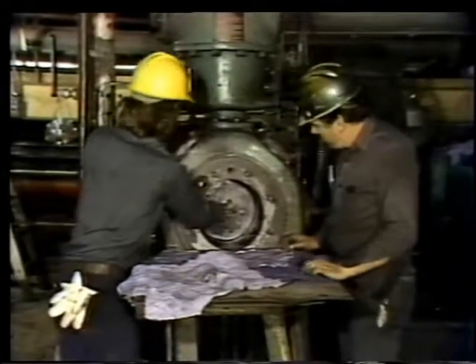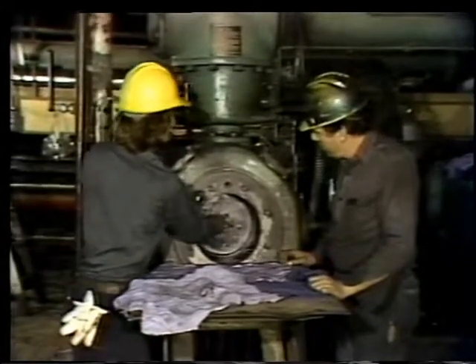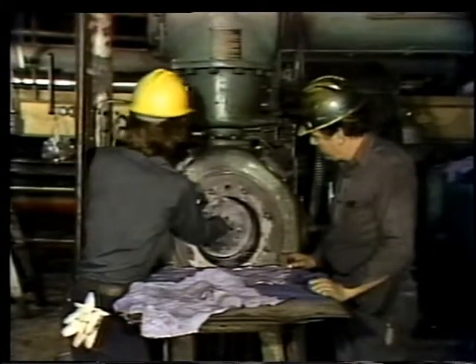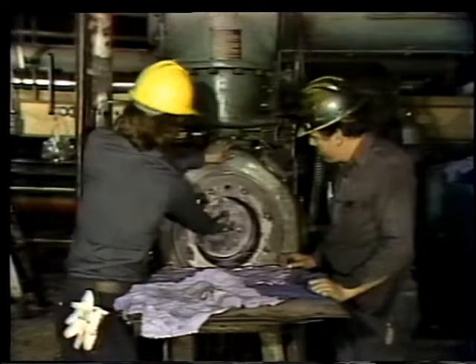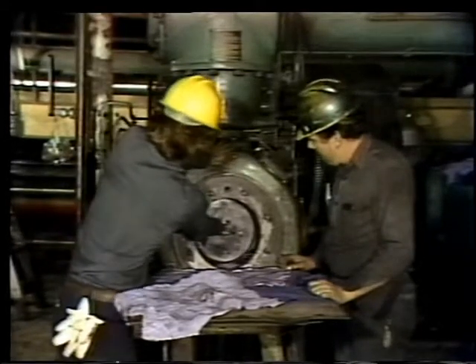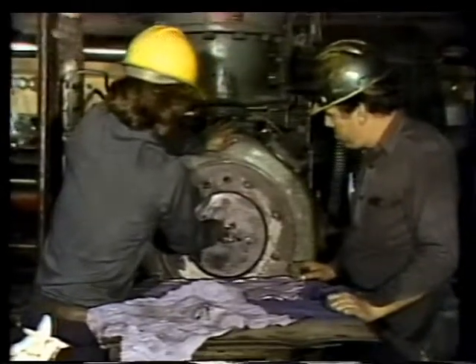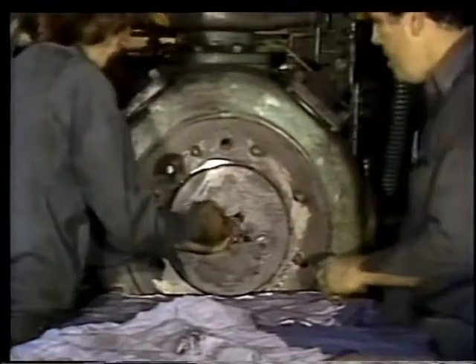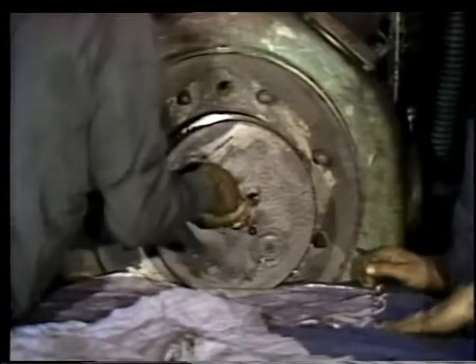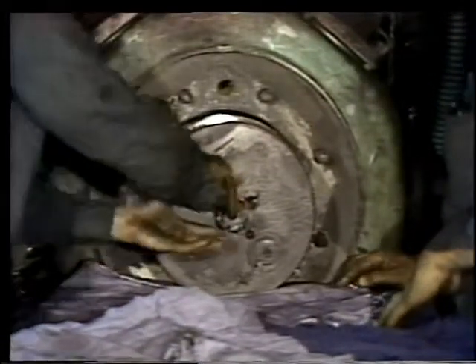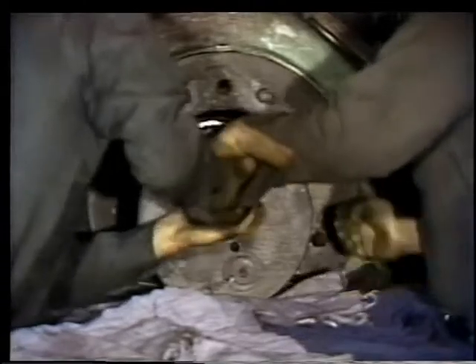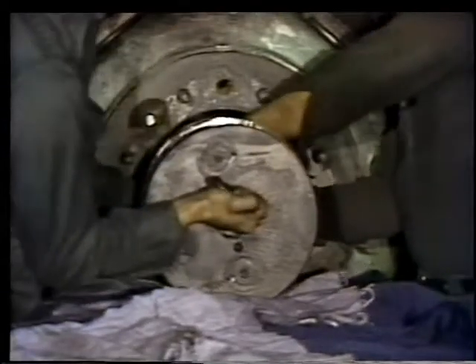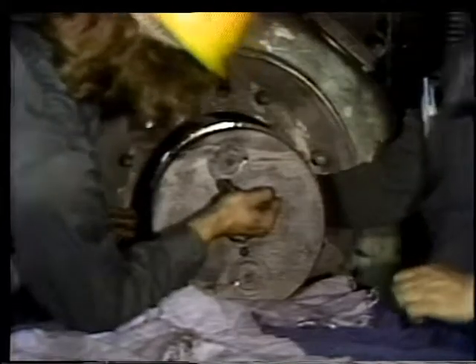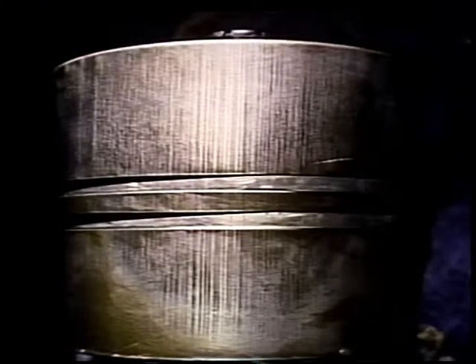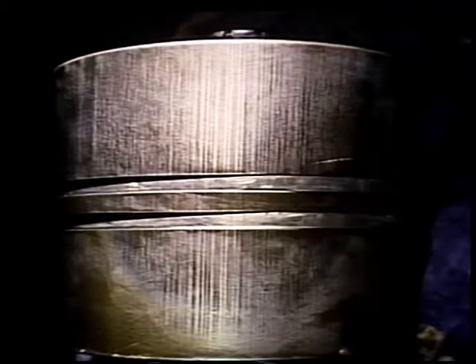With the table in position, you screw an eye bolt into the piston. This enables you to pull the piston out. With the piston removed, it's inspected for signs of wear. These wear marks were found on the bottom of this piston.